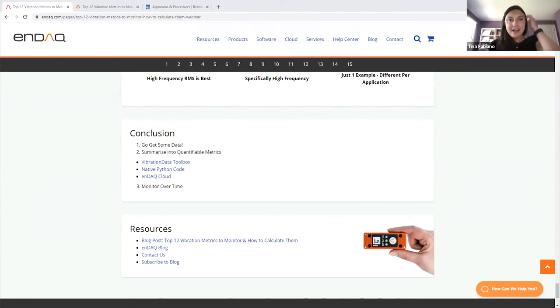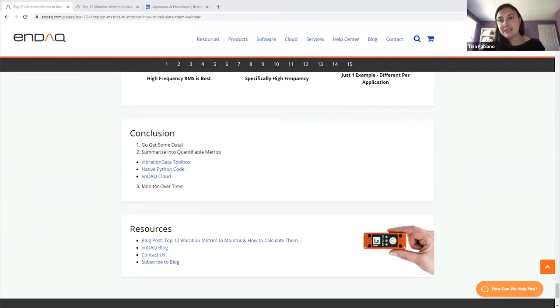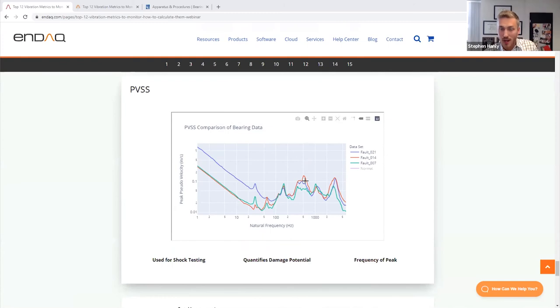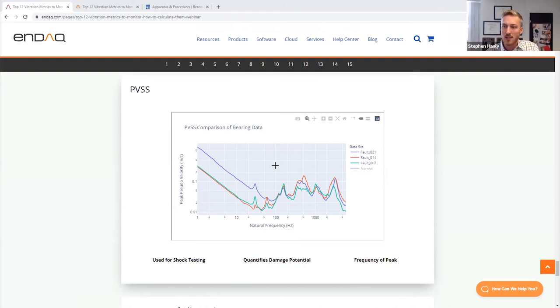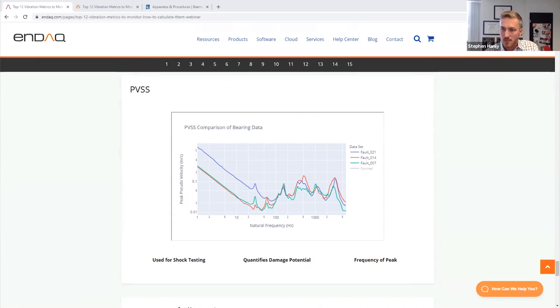Question: Of these 12 metrics, which would be applicable in analyzing impact-related accelerations? That's a great question — that's exactly why I shared the shock response spectrum. If you're doing impacts, that's what I focus on. The shock response spectrum — where is my peak, and what is the frequency of that peak? That's what I would look at for impact transient events.